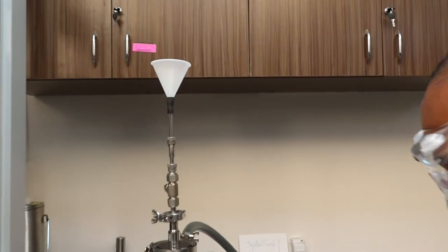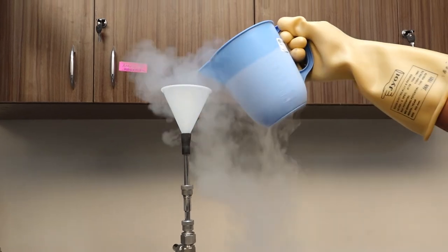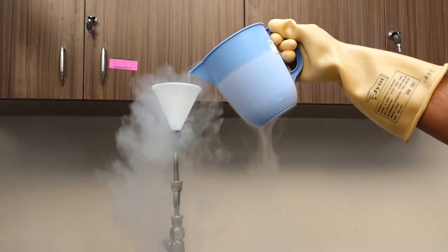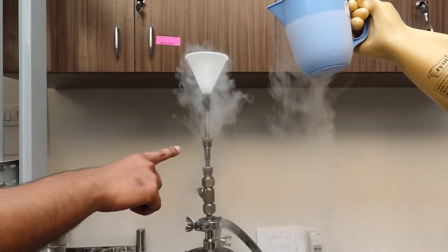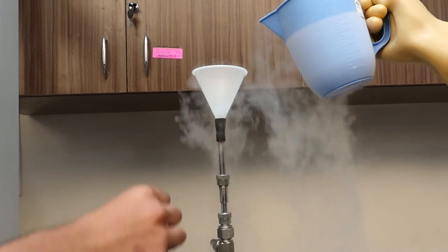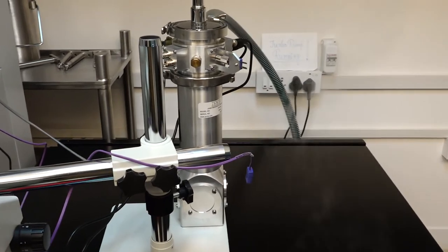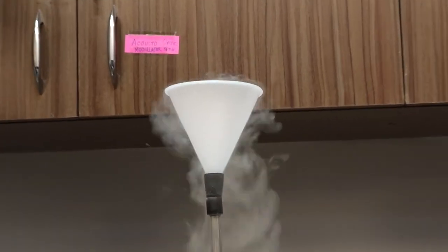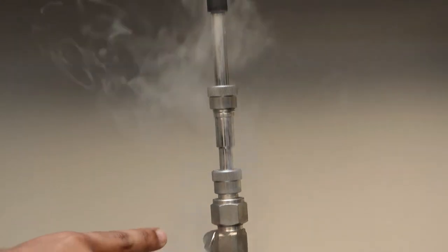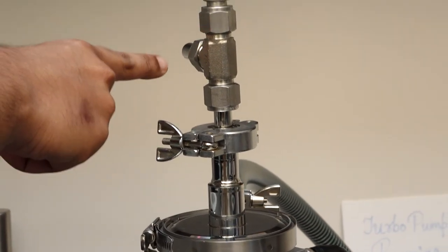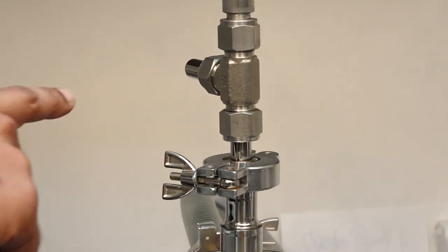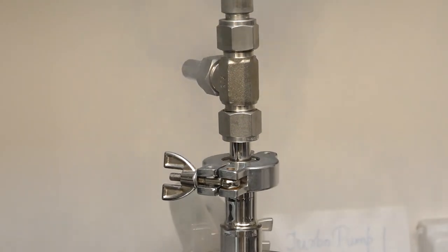To do that, we'll pour in liquid nitrogen as demonstrated here. We remove the knob here and then we put in this funnel, which guides the liquid nitrogen down to the cryo chamber. While filling, one has to note that when this whole column is filled up, we'll see vapors coming out from this tip, from this point. So we have to pour until this point starts giving out nitrogen vapor.